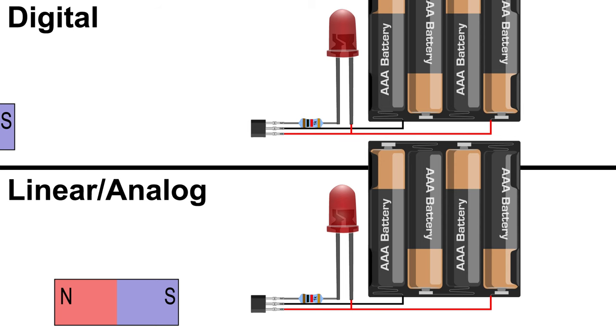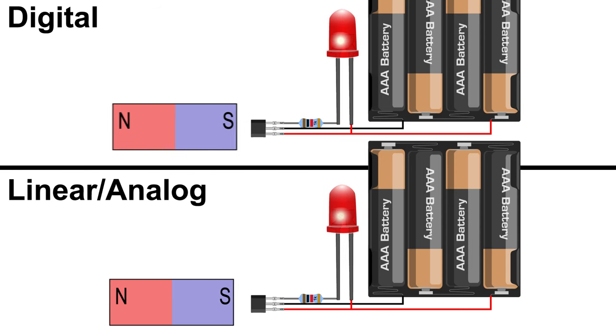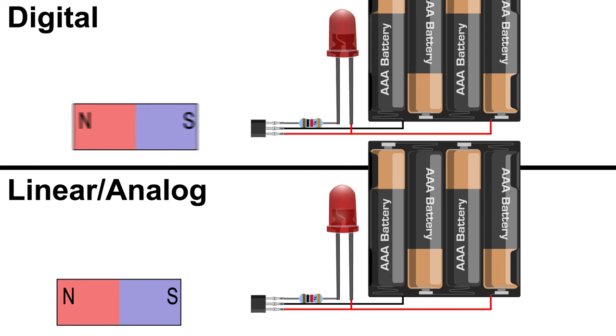Hall effect sensors are usually used in one of two sensing configurations, with either the magnet approaching the sensor head-on, moving in and out, or a sideways detection with the magnet moving left and right in front of the sensor. Head-on detection works as a proximity sensor, varying the signal distance between a magnet and the sensor, for either digital switching or linear analog signal detection.